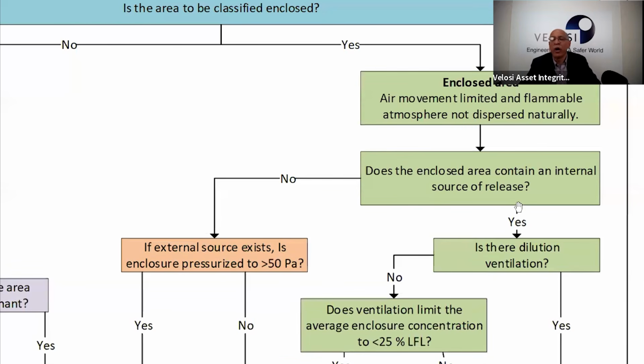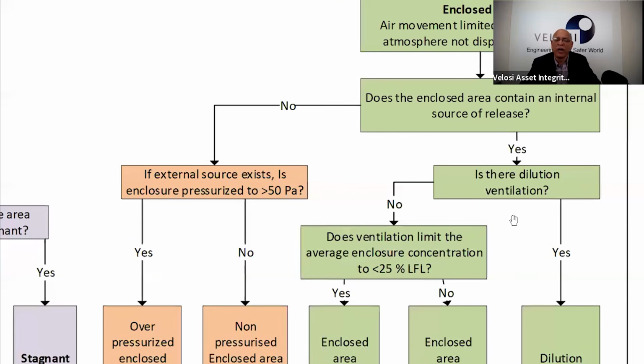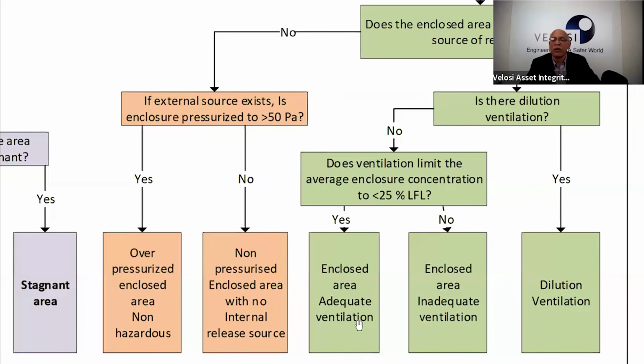But if a point source is available inside the building, like in a warehouse or some other facility with enclosed walls, then in that area, is there dilution ventilation? No. Does ventilation limit the average enclosure concentration to less than 25% LFL? Then yes, it is an enclosed area, adequate ventilation is required. If no, it is an enclosed area, inadequate ventilation. Then, is dilution ventilation applicable? Yes, dilution ventilation is required.